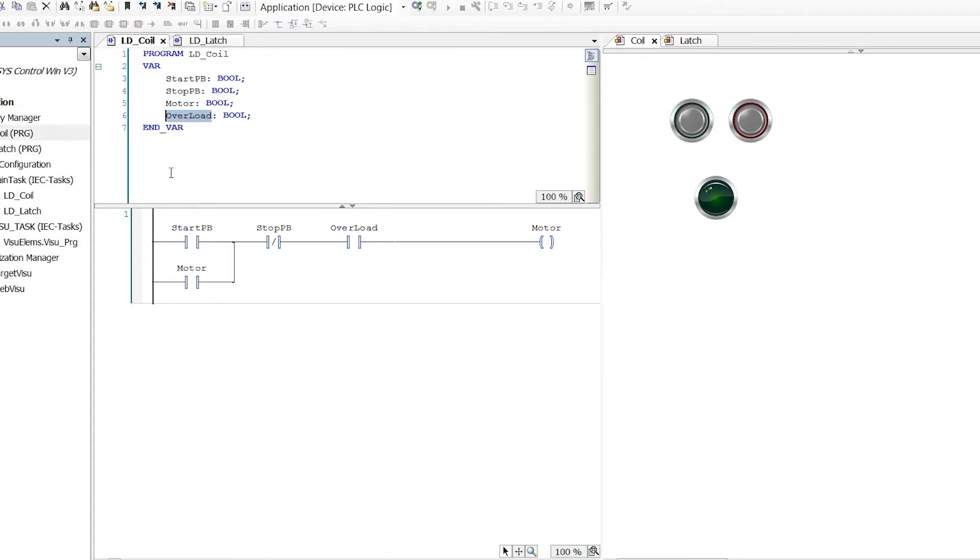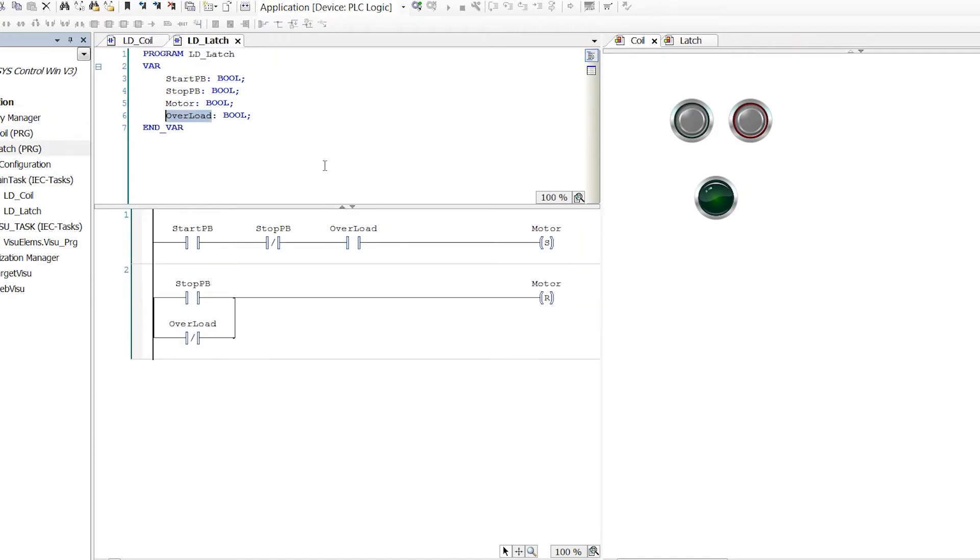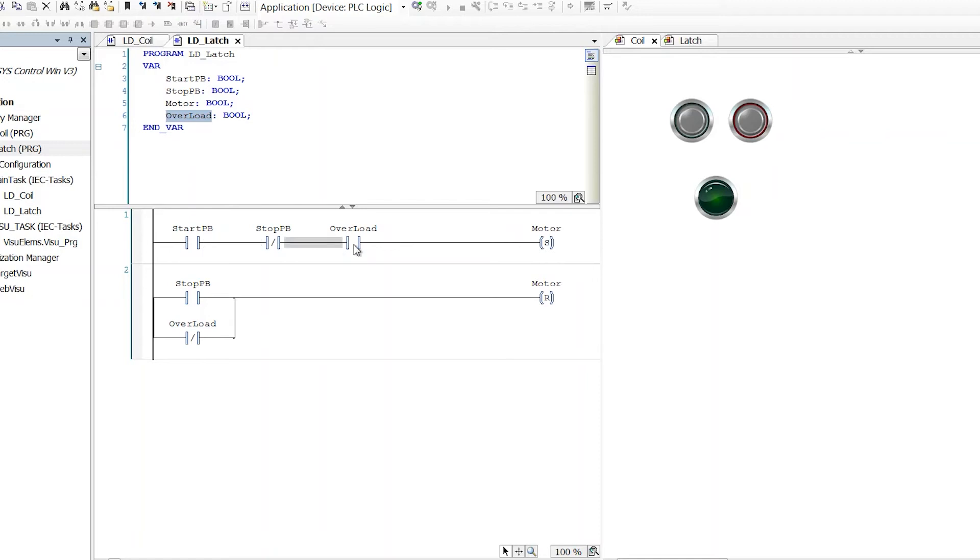So if we look back here again, we had start condition, stop conditions, latch. You'll notice when we come here, the start condition and the stop conditions are both in the, we can consider this the turn on rung. This is the thing that turns the motor on. And we have to do that because we don't want to turn the motor on if the stop conditions aren't in the right state either.